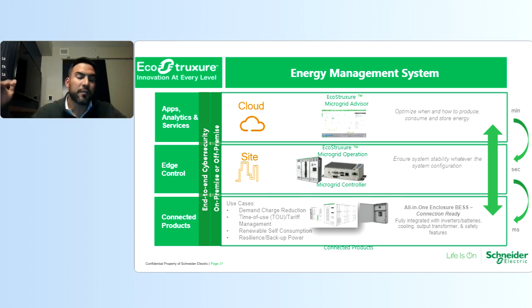And then you have the supervisory microgrid software platform, which is a cloud or analytics service that basically monitors the entire microgrid, your PV production. It takes advantage of time of use rates, monitors utility rates to optimize when to produce, consume energy, or store energy. It really is the intelligence behind your microgrid system, right? And most energy management systems will offer this type of service, but this really offers the next level, you could say, analytics to make sure that your microgrid is making money for you. And additionally, for specifically those grid connected services where your utility is present.